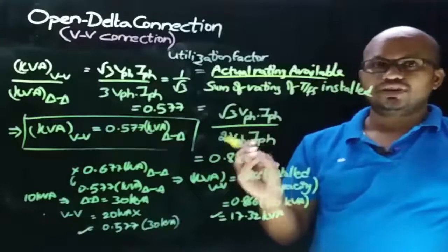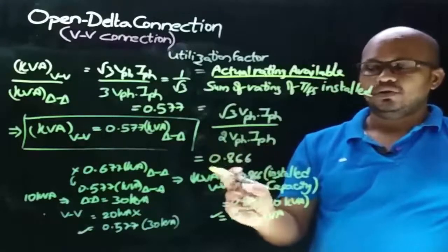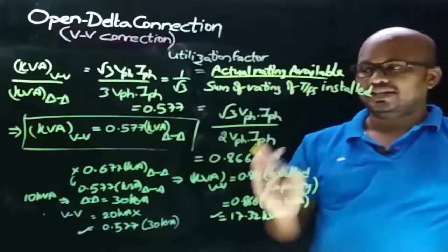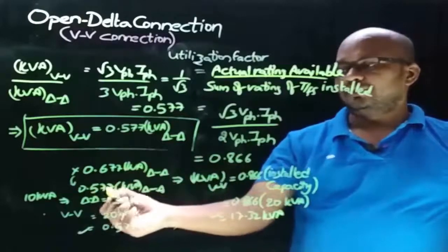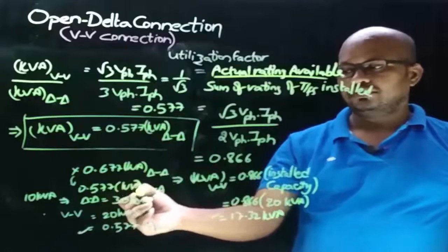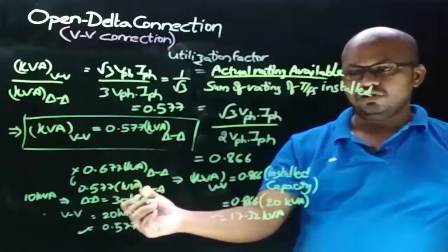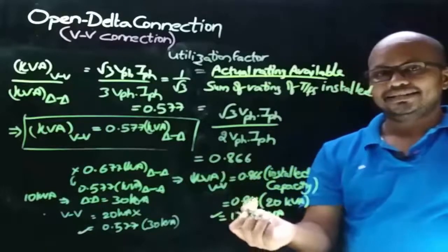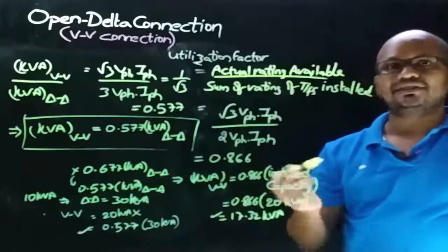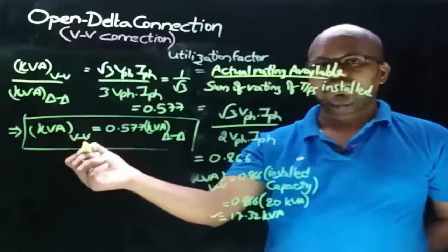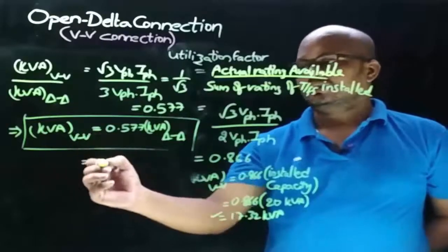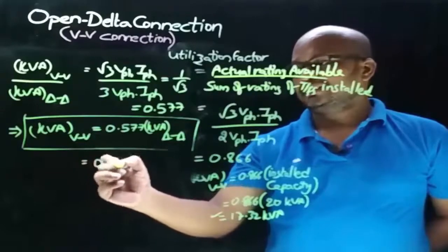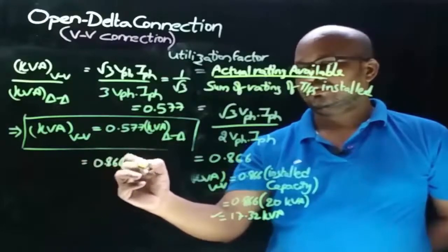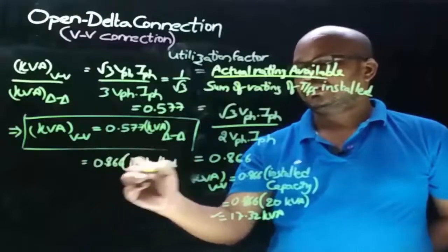That is, if you want to find the power delivered to the load by open delta connection, we can take 57.7% of the delta-delta connection rating or 86.6% of the installed rating. That is, you can take the kVA rating of open delta connection is equal to 0.866 times the installed capacity.